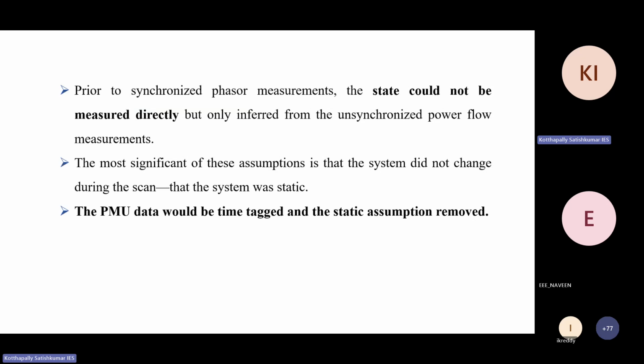As I told, the problem with the SCADA system is that it will not take the data at the same time from all the substations. They are measured at different times. As the system is dynamic, when you take the measurements of all the substations at different times, the data is not accurate, because you are measuring at different times. You should measure exactly at the same time to know the system state. Here, in the static assumption, we assume in the state estimator that the data is static.